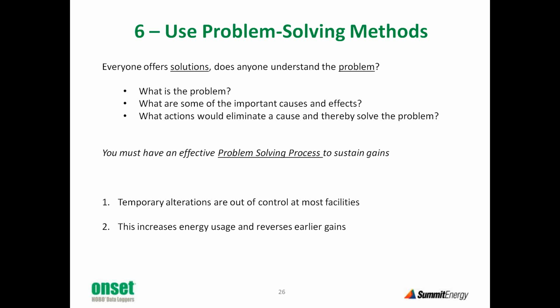Just a quick example. Let's say the problem is I'm a food plant and I've got condensate dripping off the ceiling. That's going to shut you down. Somebody says, well, I think the issue is these dampers. They're closed. We need some more outside air. Somebody jams a 2x4 in the dampers. Condensate goes away. Problem solved, right? Well, not really. Jamming those dampers open has made a temporary alteration to the control system. Maybe there's a better long-term solution.